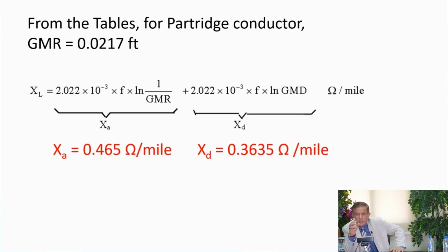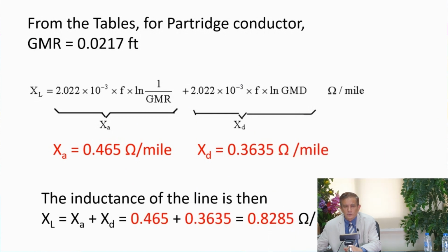Now we do this to understand the data sheet. Why did they split it into two parts? One part is dependent on the conductor, the first one, which has GMR. The other one is dependent on the GMD. This makes sense because the manufacturer is trying to give you the information for this conductor. The spacing is yours, based on your design, your installation, voltage level, whatever. This first part is shown in the data sheet, and if you sum them together, you get the total.